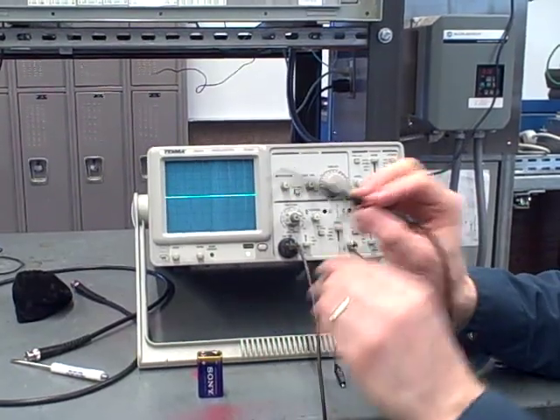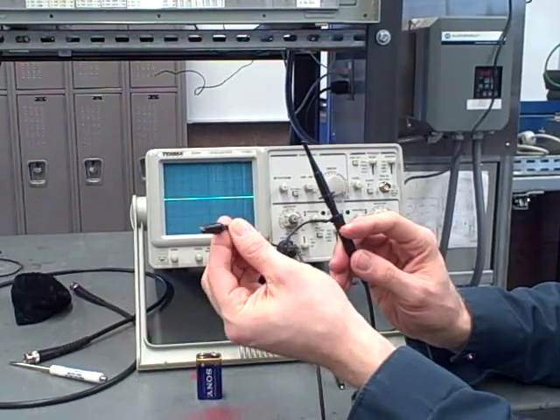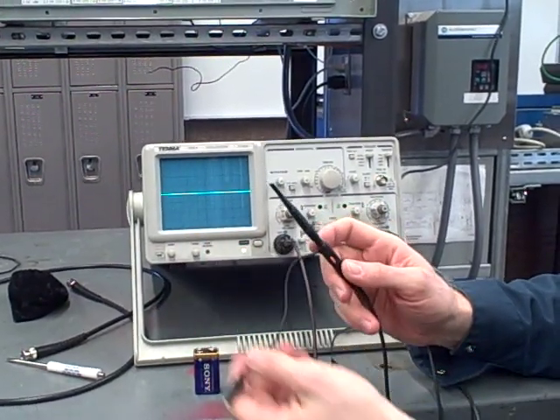So every time you make a connection to a circuit like this, you are grounding one part of that circuit whether you like it or not. You better be prepared for the results. So you cannot be doing phase-to-phase measurements on an AC system. Otherwise, this thing would be a direct ground fault. And like I said, if you're holding it, it's going to be very, very nasty.